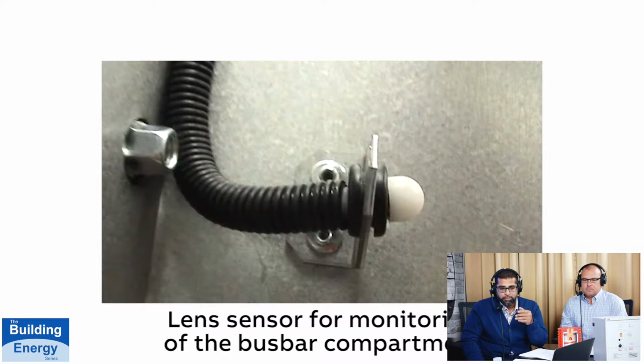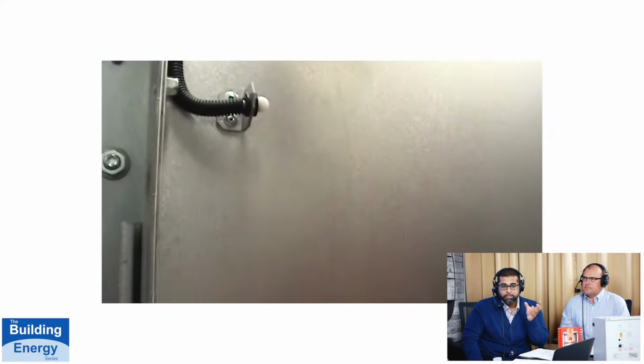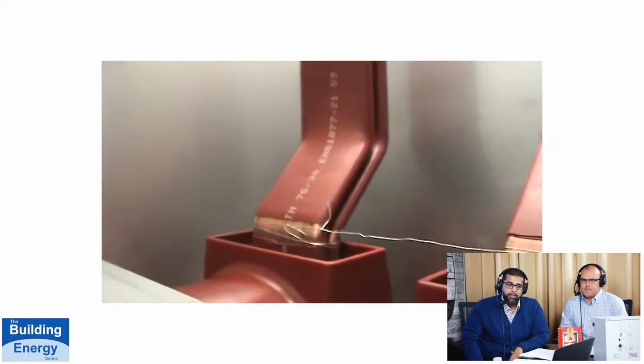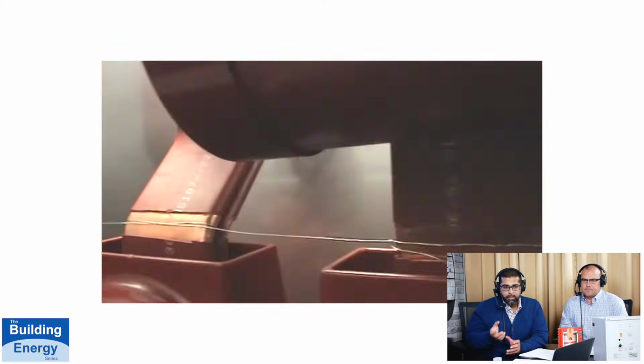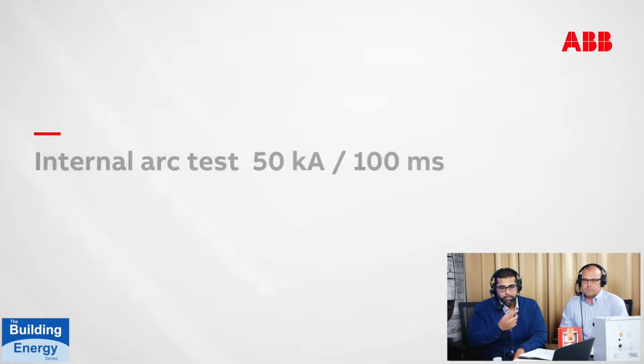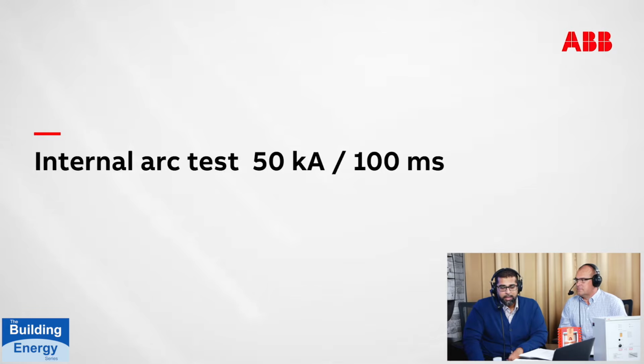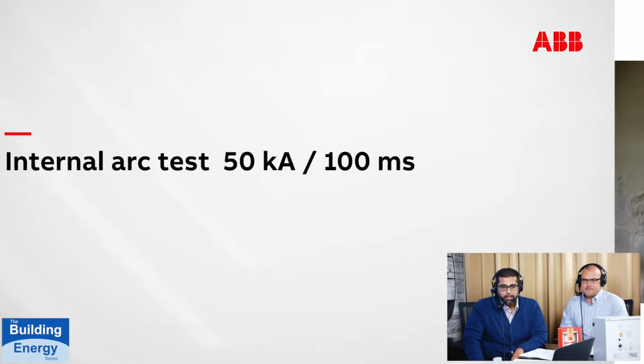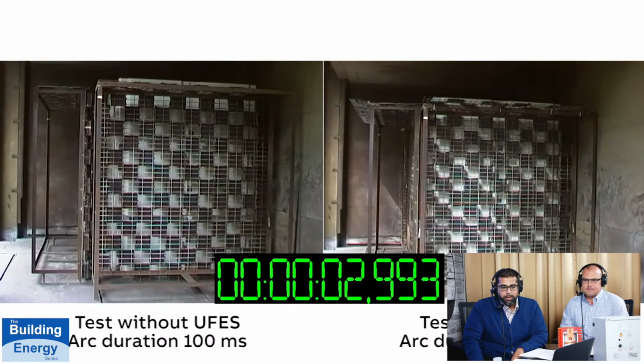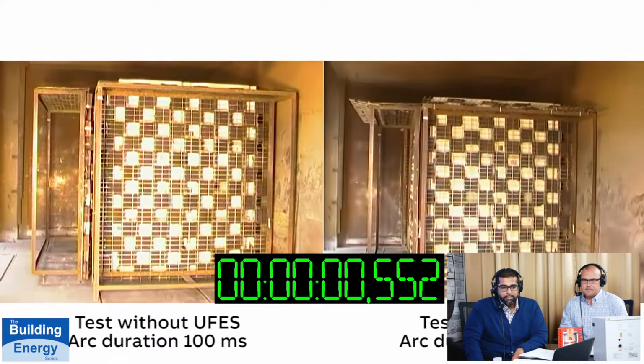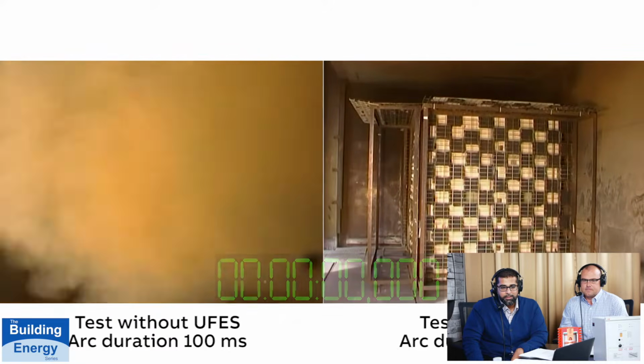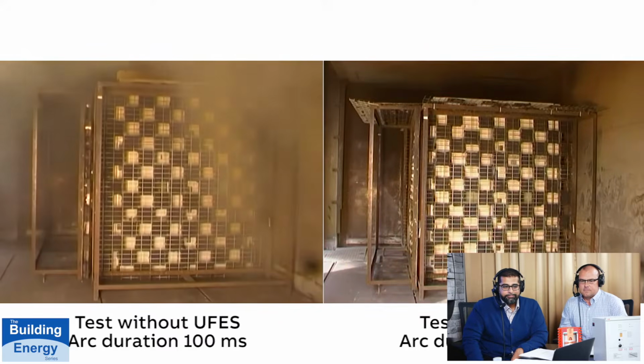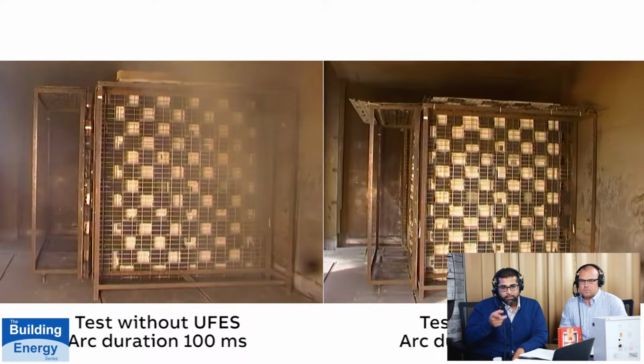Now, these are the lens sensors. This is what will detect the presence of overwhelming light in the compartment. And obviously the current, it's connected to a CT input in the back of the unit as well. Now you'll see the internal arc test at 50 kiloamps for 100 milliseconds. On two sides, on your left-hand side is switchgear without the UFES, and on the right-hand side, switchgear with the UFES. The next few seconds will show the amount of damage that takes place.